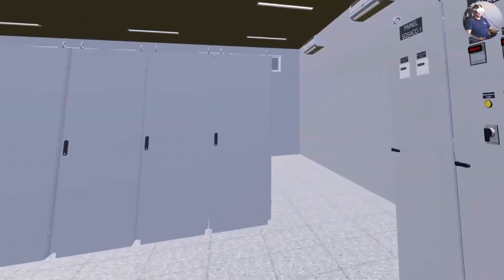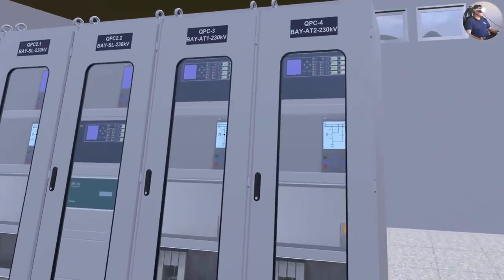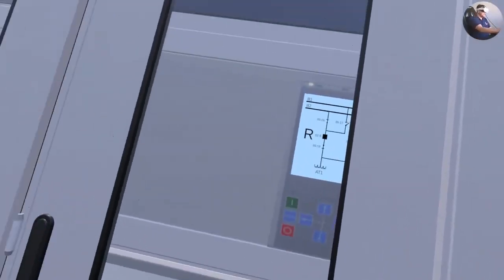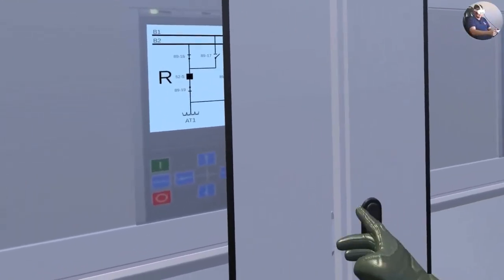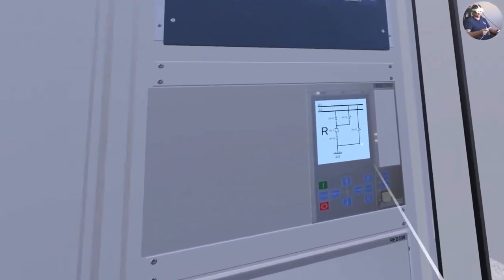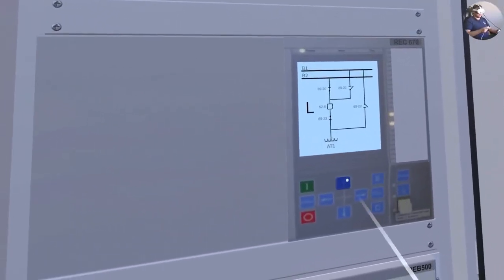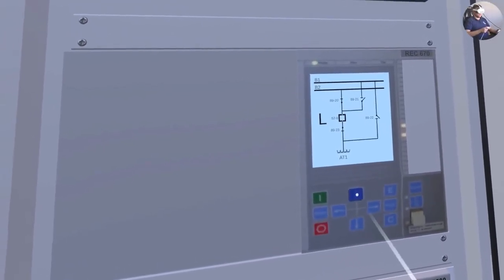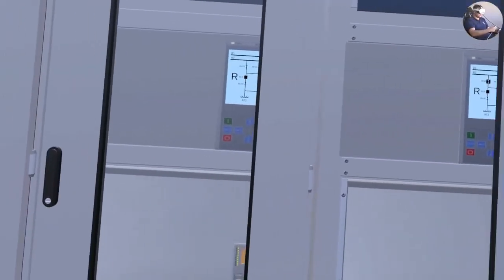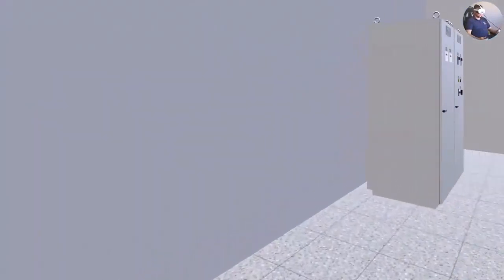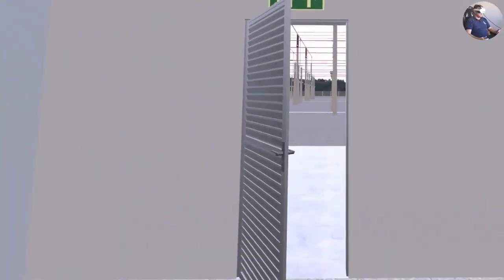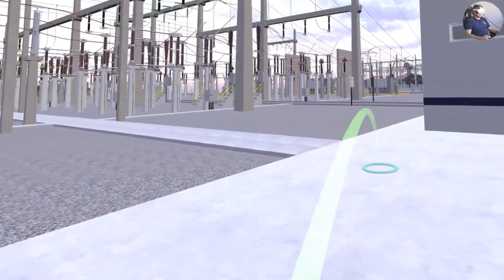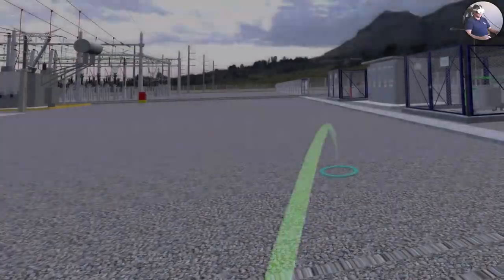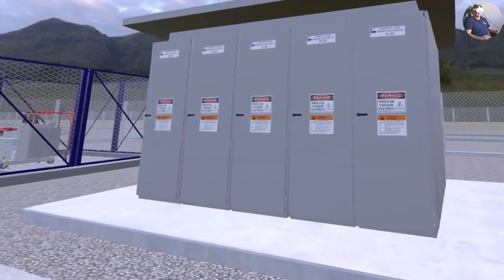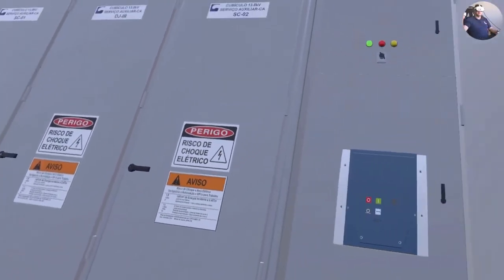So let's go here. Let's locate the AT2 panel here, right? AT2, we can see there that it's open, right? Over here we have AT1, circuit breaker closed, disconnect switch is closed, and here we see that we have the circuit breaker open. Look, the breaker is open, right? So we're going to switch to local and select the equipment here, circuit breaker. Let's give the closing command, breaker close. Let's switch back to remote, close the panel. And now let's close the circuit breaker at the cubicle of 13.8 kV. Let's open this panel here. Let's give the command here now. Through the supervisory system, let me switch over to remote here now. And let's do the closing here.